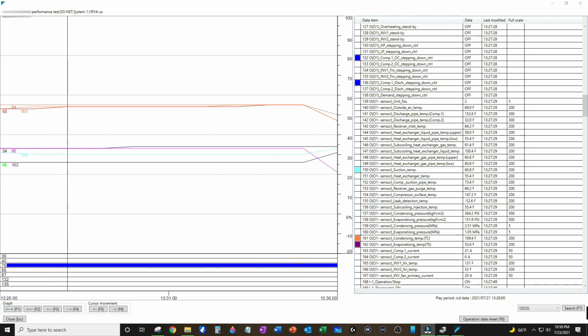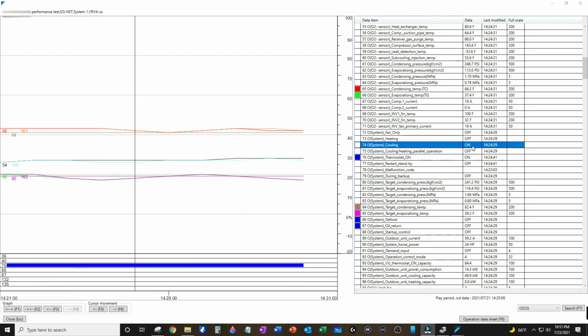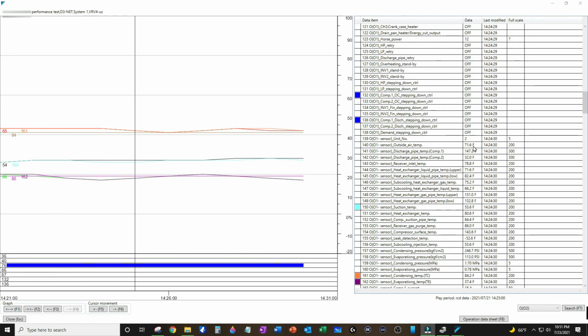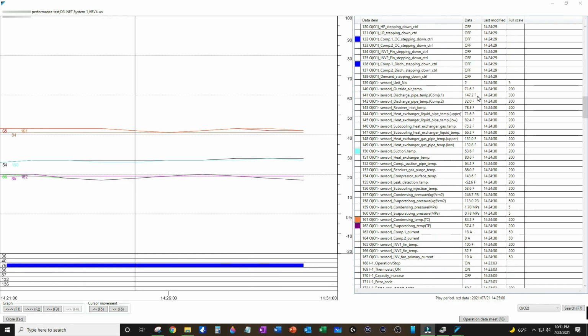After running heat mode for a little while, I set everything back to the cooling mode so I could take some performance checks in cooling. Again, I'm going to make a similar loop as before, but in the opposite direction. I always start with the compressor. Discharge superheat looks okay here. It's not optimal, but it's within normal range. The outdoor coil temps look good. You can see hot gas condensing to liquid properly here, which indicates correct flow direction through the four-way valves.